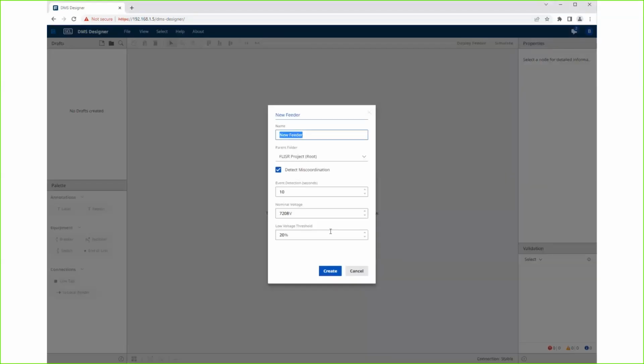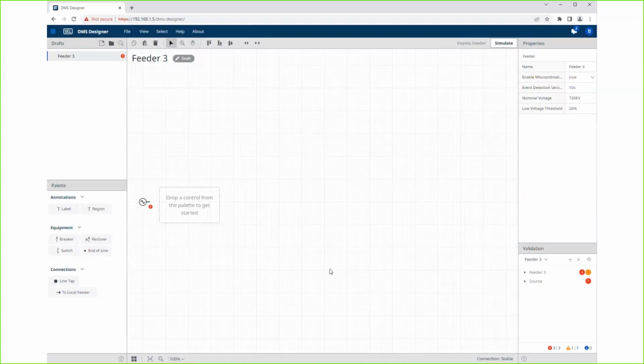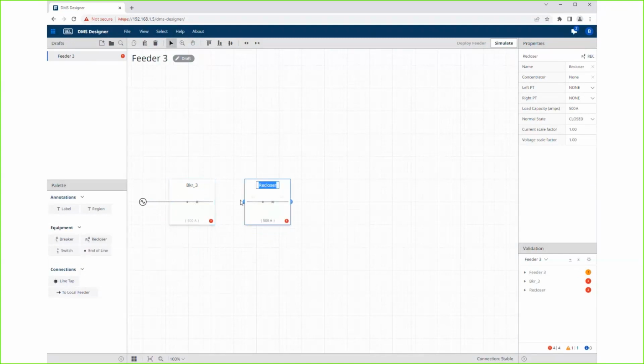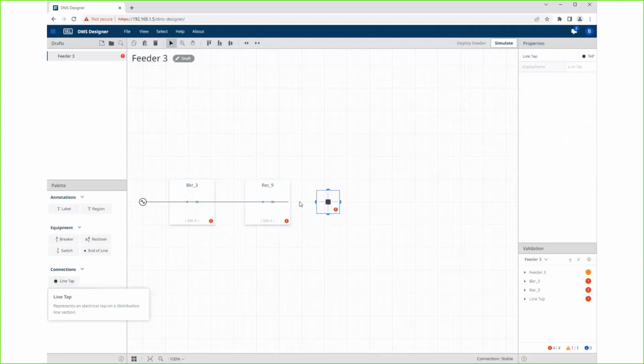So I'm going to create a new feeder. I call it feeder 3, and there's only one setting there, right? Do we want to detect miscoordination or leave it alone? And there are a couple other threshold type settings in there that I can go into details on if any of you would like to contact me. I'm happy to dig into this however deeply you'd like. But what I'm doing now is I have this blank virtual whiteboard. We call it a canvas, a feeder canvas. And what I'm doing is I'm dragging breakers and now a recloser onto the screen and connecting them as they are connected in the real world. This is what teaches FLISR how to contextualize the data that it gets when it talks to breaker 3 or recloser 9. So I've added a line tap.